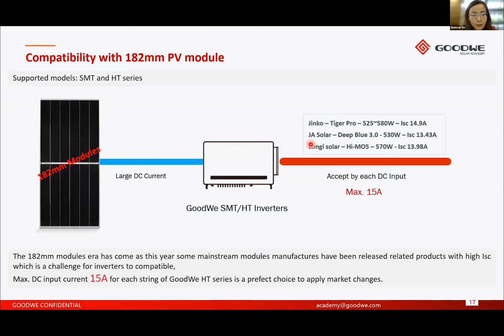We can see that there are some mainstream 182 manufacturers that have a short circuit current of about 13 to 14 ampere. And we found that even the one with the largest short circuit current, Jinko, that has 14.9, is also below 15 ampere, which our inverter can support. Because our inverter can support a maximum of 15 ampere input current per string. And it is already a mainstream combination for the 182 modules and HT inverters. So we are fully compatible with the 182 millimeter modules.